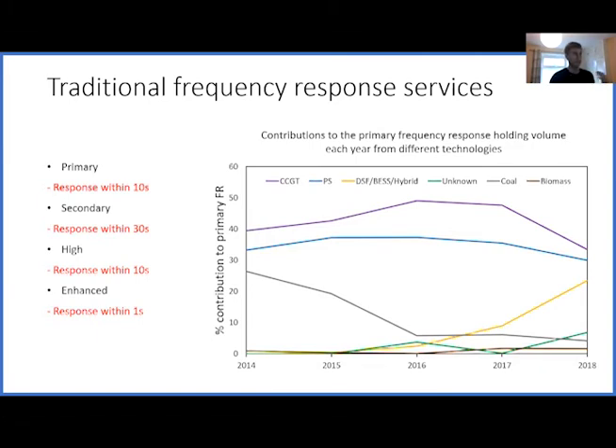If the frequency goes below 50 Hertz, you have primary and secondary frequency response. Primary is the first responder and needs to respond within 10 seconds. After that, secondary takes over and is longer duration. Then when the frequency is above 50, you've got high frequency response, which basically does the job of primary and secondary in that it has to respond quickly but last indefinitely on the high side.